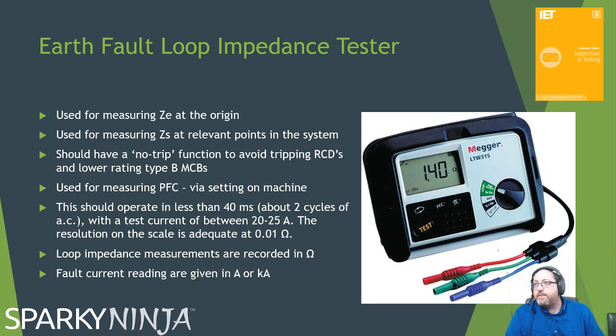Other test instrument, the earth fault loop impedance tester. We'll use this for verifying the supply earth at the origin. The Ze will measure the earth fault loop impedance at points through the system, at sub-distribution boards, and at every point of utilization of a circuit. So the Zs. We can also use it, you'll see this picture here, there's a PFC button on it. So we press that button and it just does a bit of Ohm's law, changes the ohms to amps. So we can also use it for measuring the respective earth fault current and the respective short circuit current.